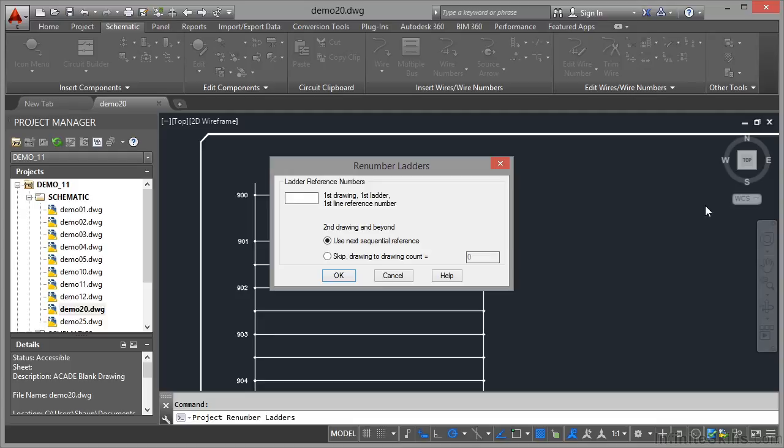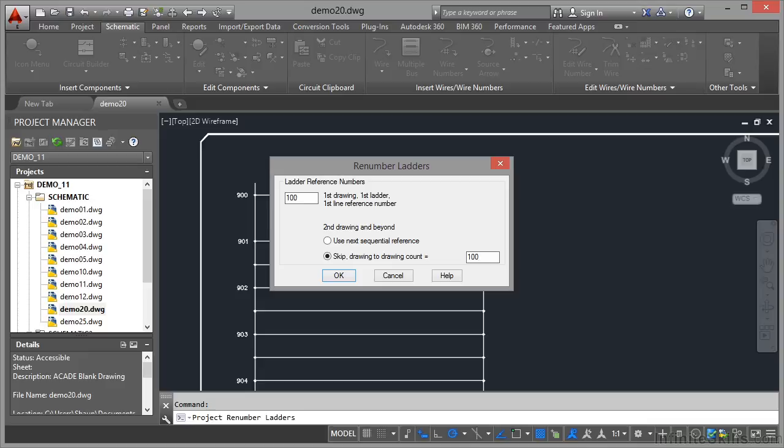Now this brings in the ladder reference numbers dialogue box. It's called renumber ladders at the top there. For the first drawing, first ladder, first line reference number, that's going to be 100. And then what I'm going to do for the second drawing and beyond is I'm going to skip drawing to drawing count and I'm going to go 100 each time. So the second drawing will start at 200, third drawing will start at 300, and so on.